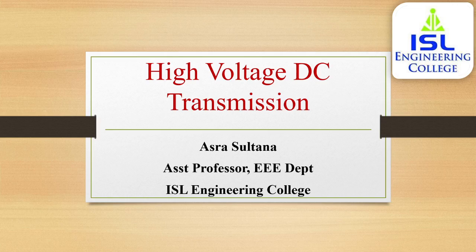Smoothing reactor we have already seen in the previous class. Now we are going to discuss the DC line. The smoothing reactor is connected before the DC filter and in series with the converters. Apart from smoothing the direct current, it also serves as a buffer between the converters and the DC line. Sizing of the reactor depends on various requirements, including the reduction of ripple in the current.